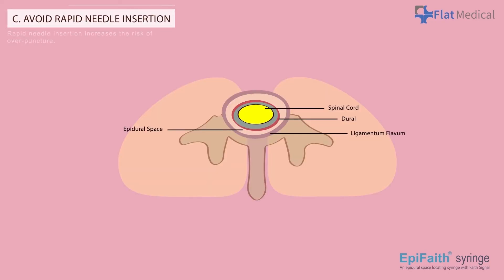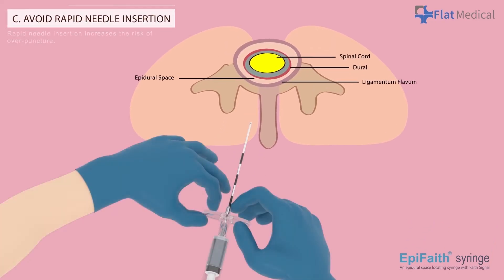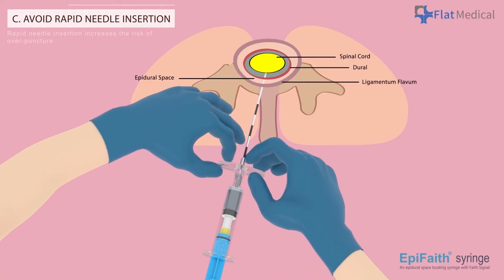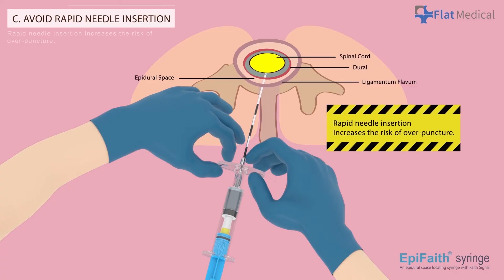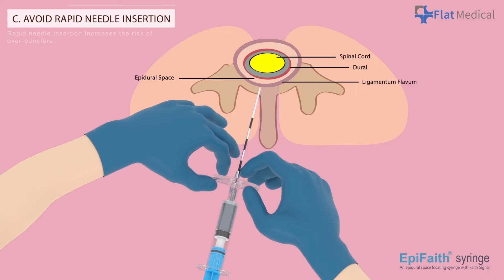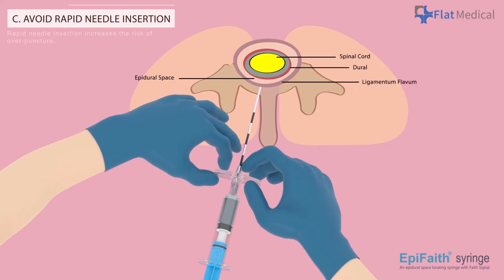Avoid Rapid Needle Insertion: Please avoid rapid needle insertion, as doing so may lead to the operator being unable to promptly halt needle advancement when the EpiFaith syringe provides signals, increasing the risk of overpuncture. Smooth needle insertion, with an immediate stop when the indicator moves, is the key practice during procedures.